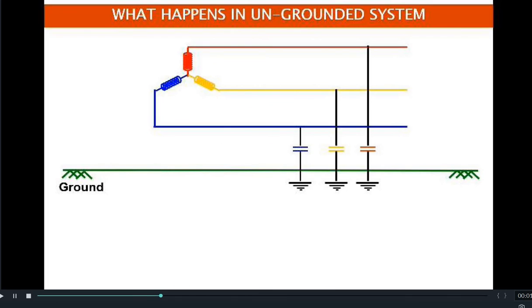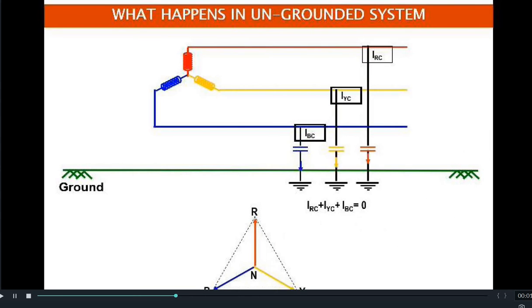In an ungrounded system, due to the transmission lines there are distributed capacitances along the line with respect to ground. There are capacitive currents from the transmission lines to ground because of this distributed capacitance, denoted as IRC, IYC, and IBC. The summation of all these capacitive currents is equal to zero.